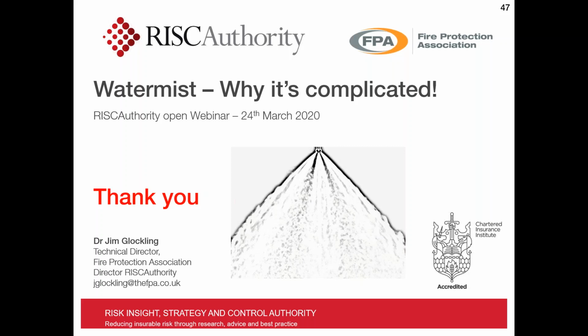In respect of high-rise buildings and water mist systems, if it is to assist with evacuation, they can be very effective in doing that. As I said, they're very effective at cooling and keeping temperatures low and stopping fire spread. If they are looking for a property protection element, because there are some requirements in high-rise buildings to maintain the structural integrity of the building itself, well, that is a different type of system altogether, and even the BS 9251 system would be inappropriate for achieving that. So there certainly is an application in the high-rise environment.